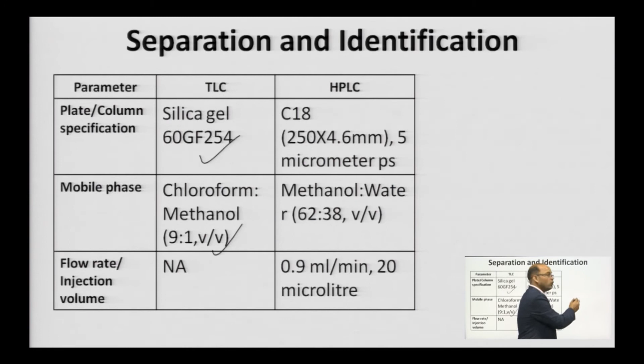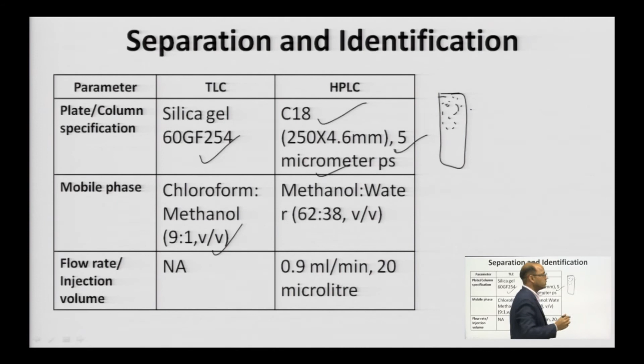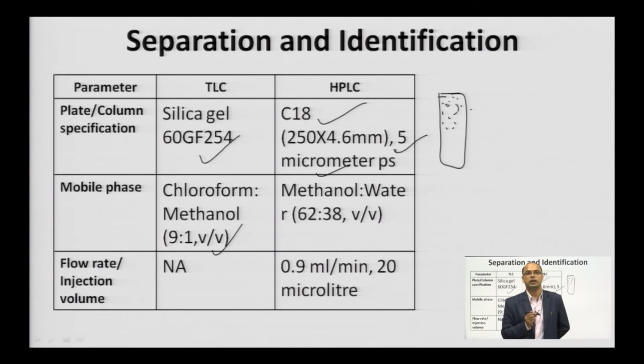If we look at the HPLC analysis, we have used a C18 column with a pore size of 5 micrometer. What is pore size? If it is the packing of your column, it means that between two particles of silica gel or your stationary phase, there is a space of 5 micrometer through which the components pass. The mobile phase for HPLC analysis was methanol and water in a ratio of 62:38 volume by volume. The flow rate is 0.9 ml per minute, and the injection volume was 20 microliter for HPLC analysis of podophyllotoxin.